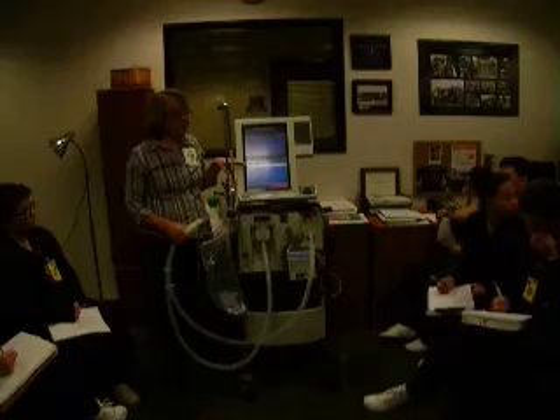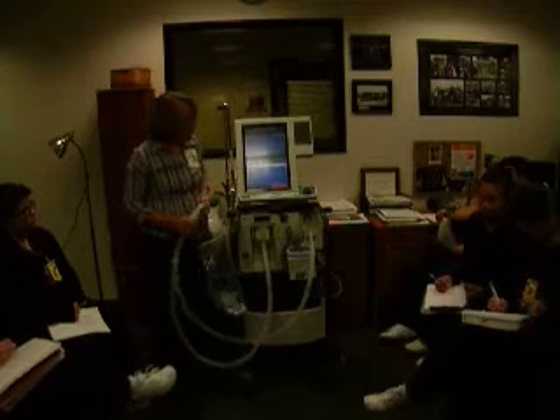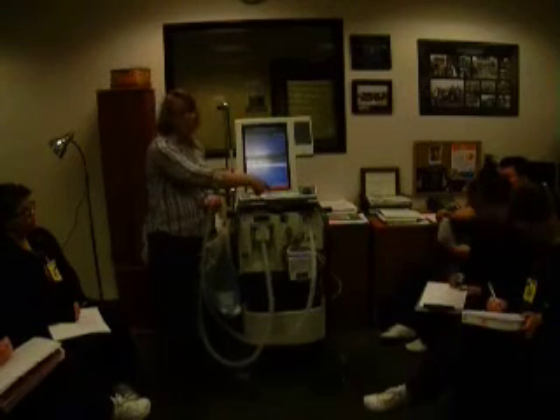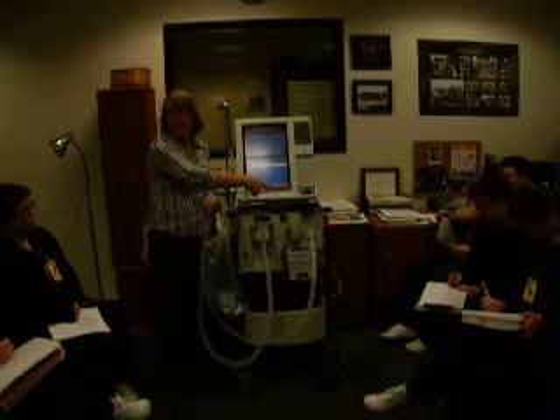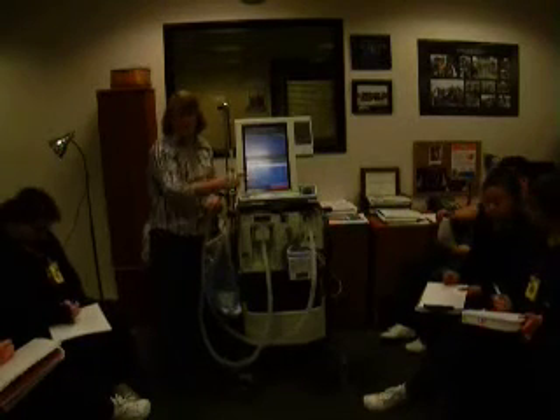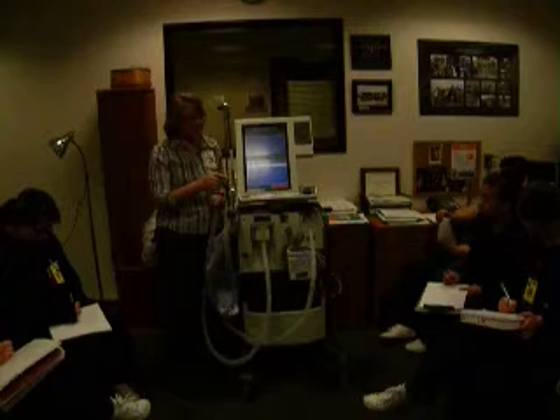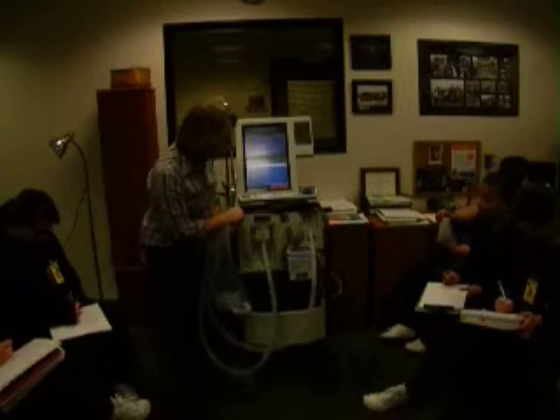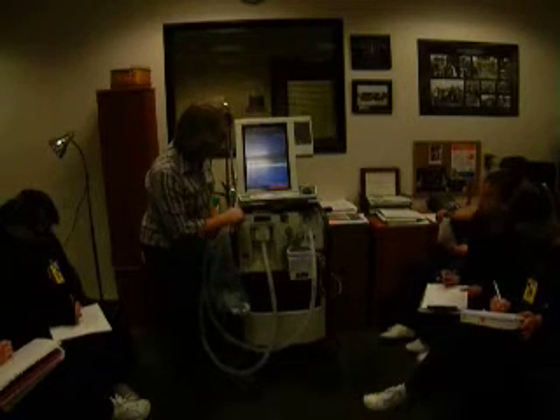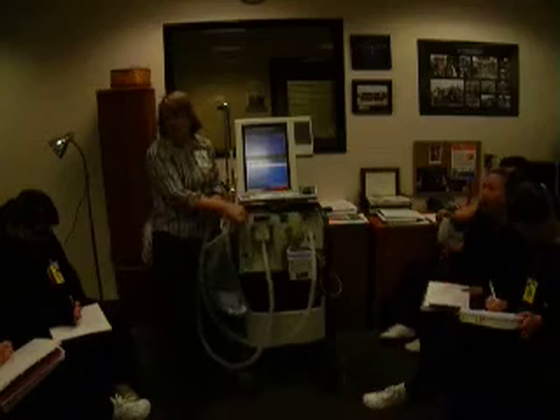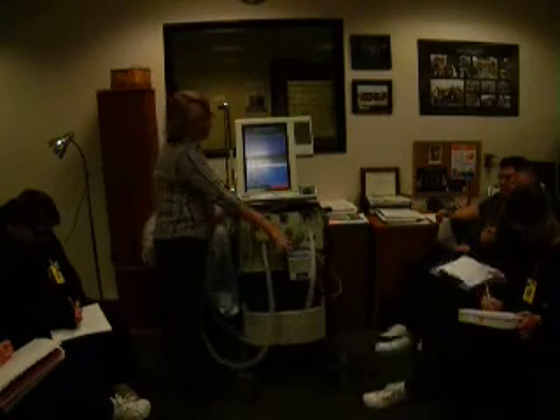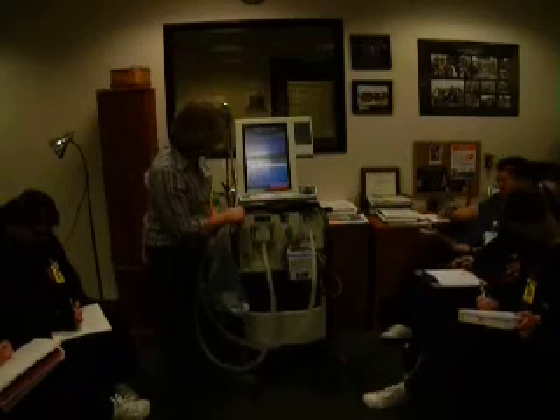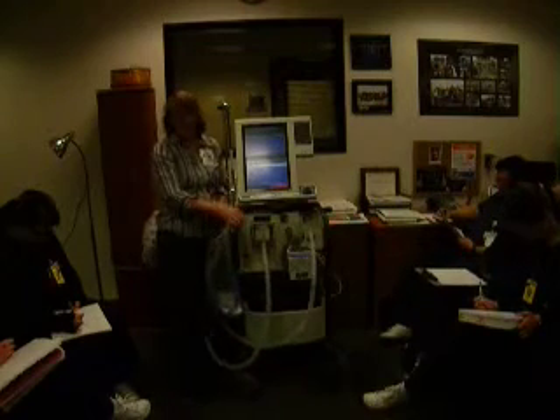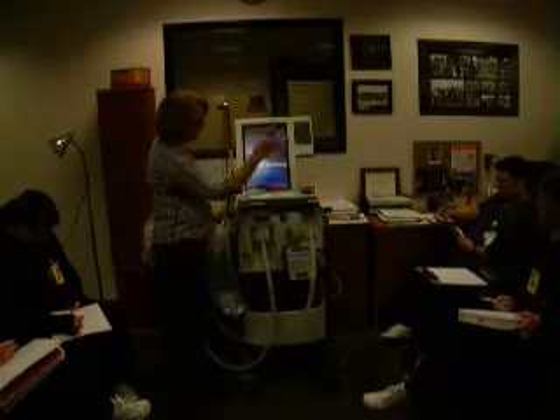Normally your oxygen would be hooked up and you would not get an alert right away. But when you do this, you've got a little orange box down here at the bottom that's going to tell you exactly what to do. You need to follow these instructions to a T or you won't pass your SST. So right now it says connect circuit with inspiratory filter and without humidifier. It's okay that there's not a filter hooked up for me, just showing you. We don't have the humidifier hooked up. And then it says when done, press accept. See, it tells you exactly what you need to know. So now we press accept.